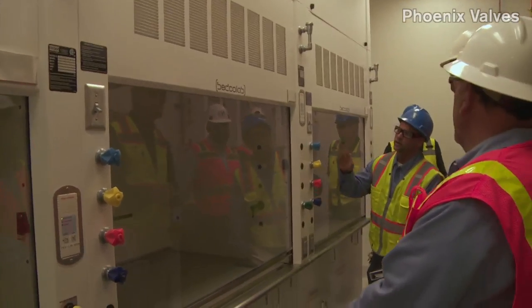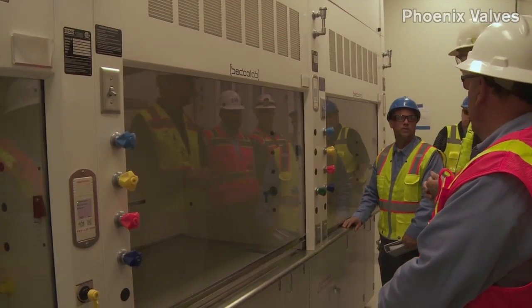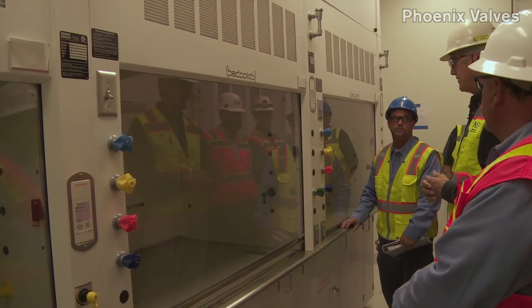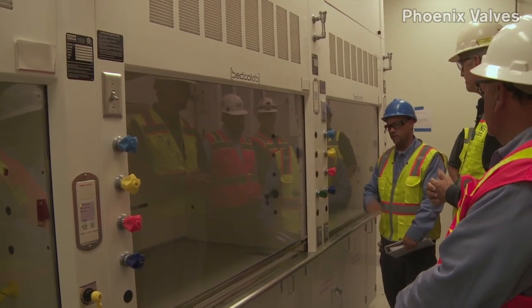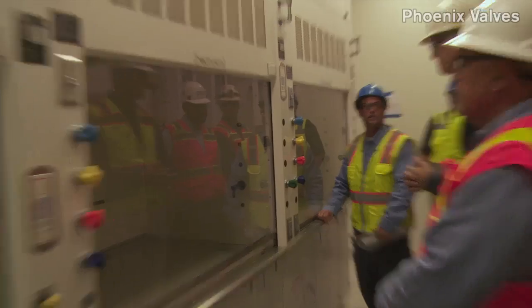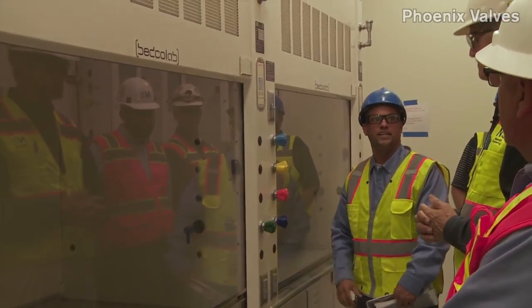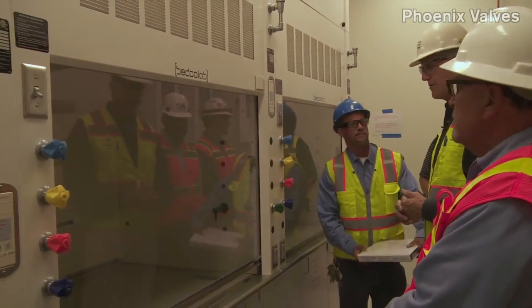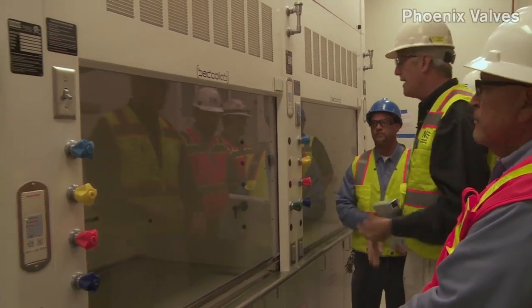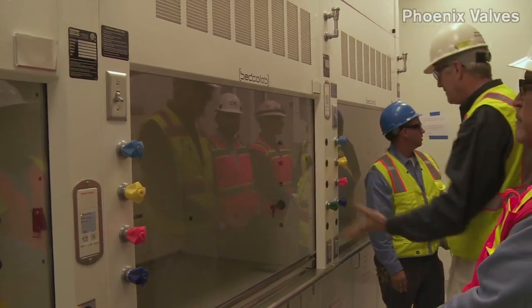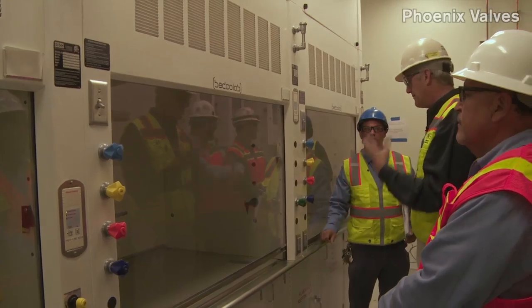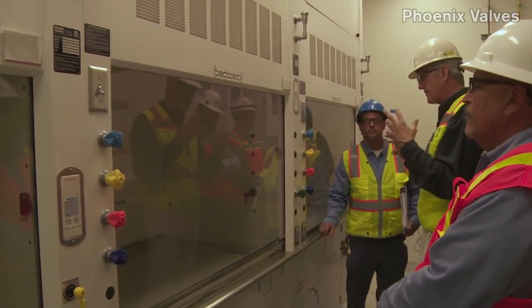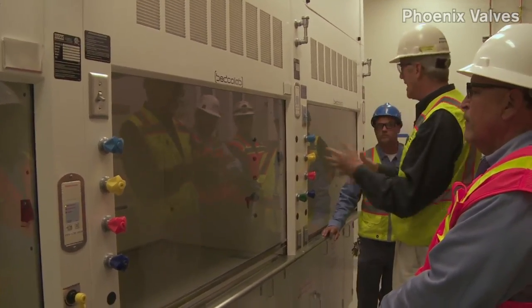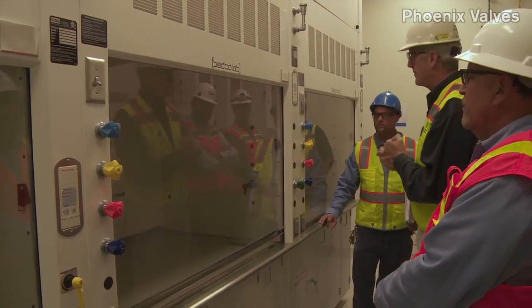Yeah, go ahead. Is there any variable air volume of fume hoods in the building? Not in this building. None at all. And the chemicals that they're going to be using are going to be just fine, not going to be using any of that nasty stuff. It's not a heavy chemical use lab, and these hoods capture just great. A constant volume hood captures well, almost as well as a VAV hood. They're both excellent capture hoods, so you won't have any problems with that.